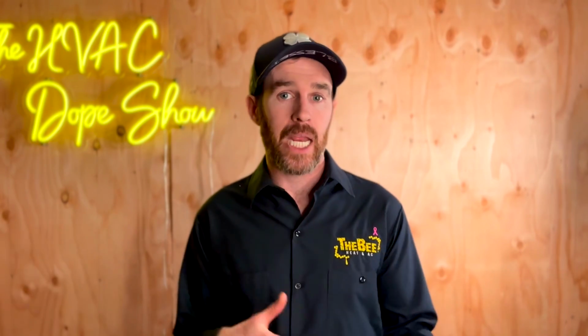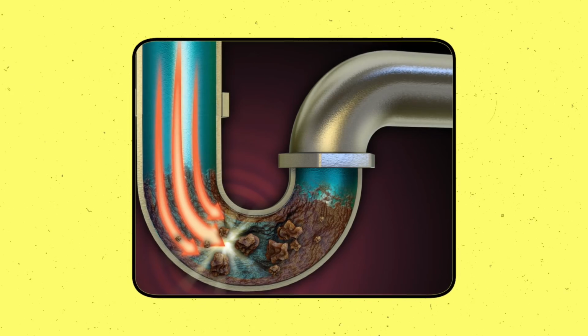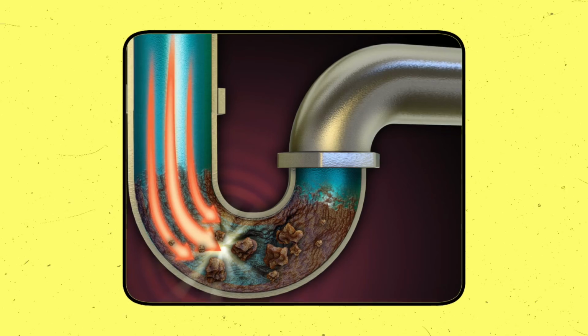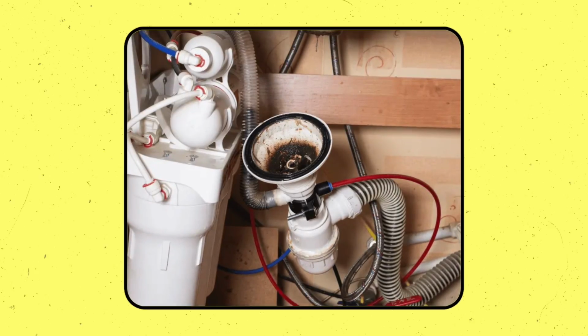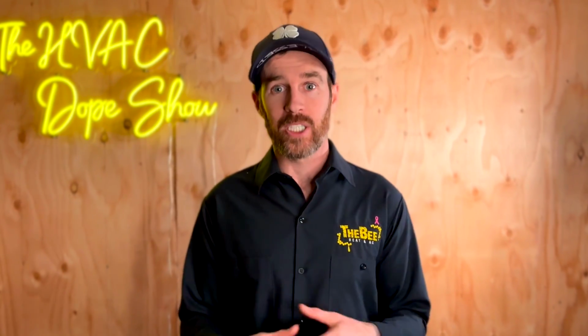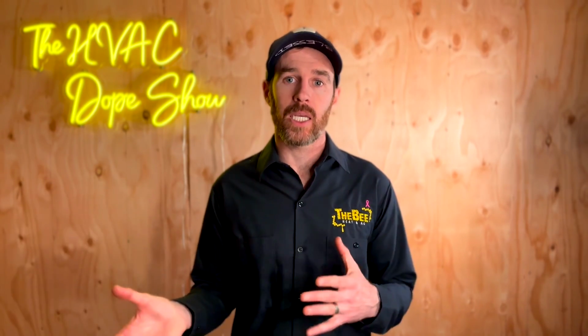If you've never had maintenance on your high efficiency furnace and it's been working reliably, you're definitely lucky, but condensate traps normally start clogging if they don't get maintenance after 3 to 4 years in my experience. And this is because sediment and dirt and debris can build up in that trap and cause the condensation to back up into the furnace and drain slowly, which is how you get that pressure switch error code that I just mentioned earlier. Now, there are several chronic issues that we see that are a result of installation error, and I will touch on these now.